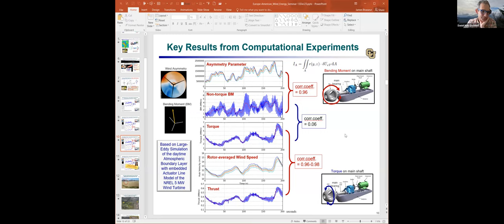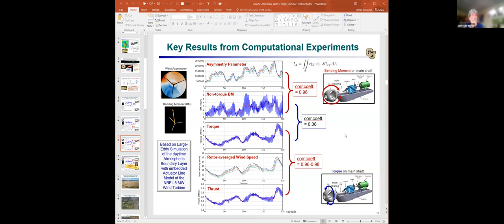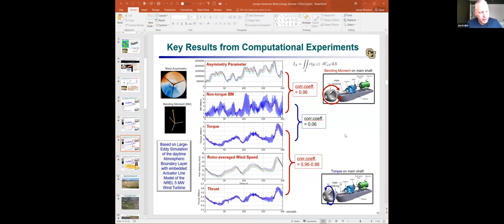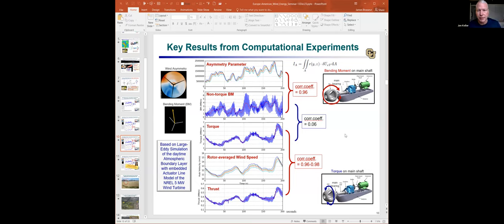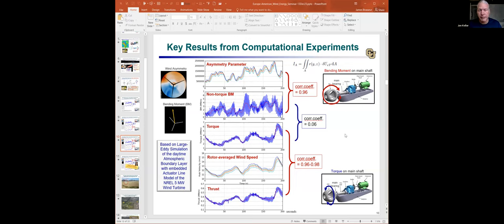Jonathan Keller adds context: for main or rolling bearings, there are multiple failure modes. For rolling contact fatigue, fatigue goes up with the cube of the load — doubling the load means eight times the fatigue. However, field data shows that particular failure mode is not what's observed in the premature failures that actually occur. Other failure modes like wear are much harder to characterize and are still being worked on.